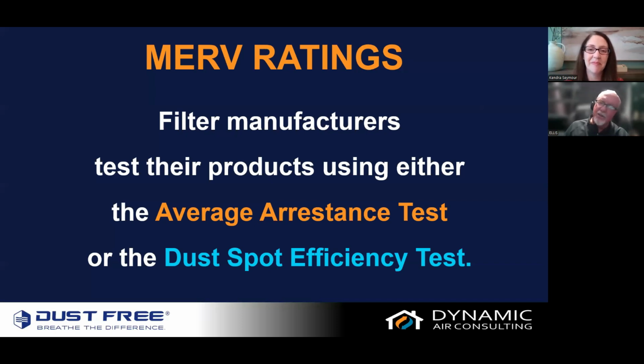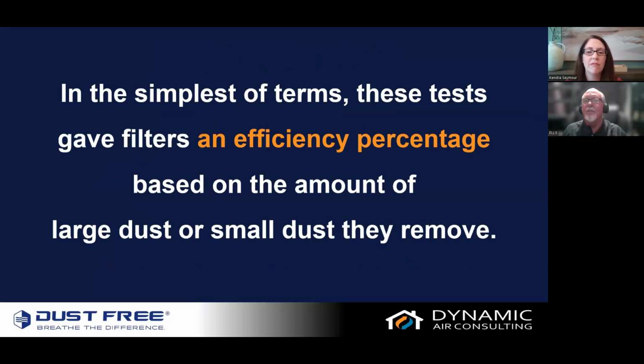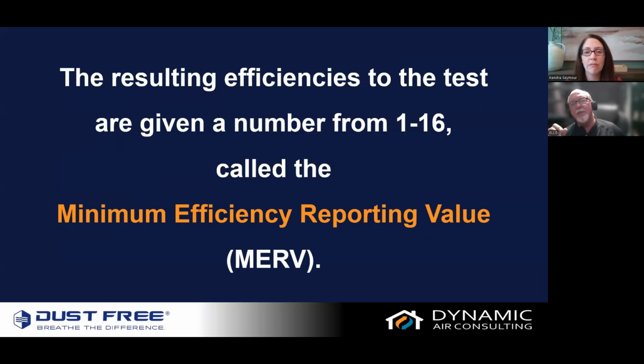So filter manufacturers test their products using what we call the average arrestance test, or the dust spot efficiency test. Most of the time, both. What this means is they have a filter, and we're in the lab, and they have a certain amount of particulate matter in different size ranges. They're going to release it, it's going to go through the filter, and they're going to recollect it on the other side, and that's going to give them numbers or data for both of these criteria. And then that's going to allow them to give their filters a rating, and it's based on the amount of dust that it removes. But it also measures airflow and static resistance too, because that's all part of the equation. This efficiency test was given a number between 1 and 16, and it's called the MERV, or Minimum Efficiency Reporting Value.